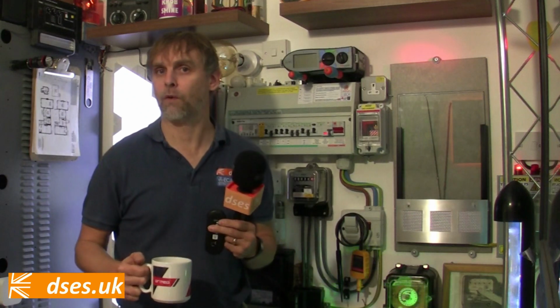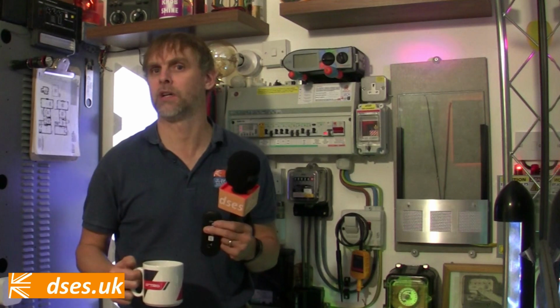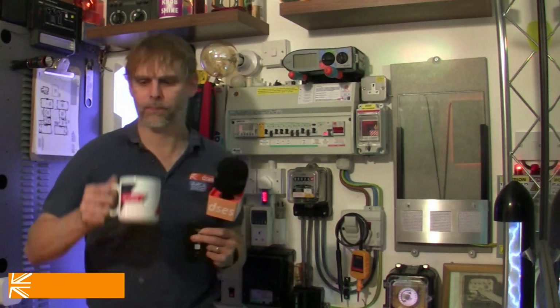Also, getting called out to an RCD trip is something one can fault find on using some insulation resistance testing to quickly narrow down which circuit is your smoking gun, whereas trying to locate an intermittent AFDD trip across a group of circuits would be a nightmare. You're looking for a loose connection somewhere and you don't know which circuit to even start with. To hell with that.